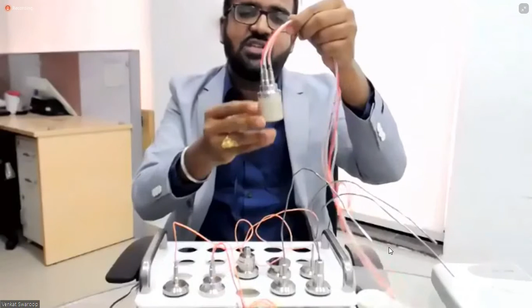The next logger I'm going to show you is a bendable one. The sensor here is stainless steel and bendable, and you can use it for dry heat sterilizers, tunnels, and other high temperature applications. The only thing to remember is when using this logger for high temperature applications, you have to keep it inside an insulating canister housing assembly, a separate housing assembly. You keep the logger inside that so the assembly protects it, and this sensor will withstand up to 400 degrees. That means you can satisfy your tunnel applications. So this is about the bendable logger.